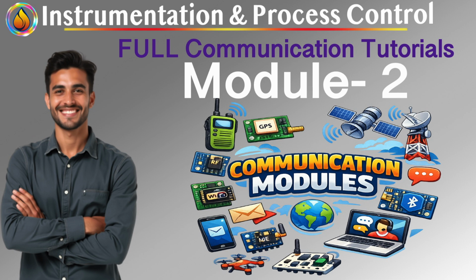RS232 didn't betray you. It simply did exactly what it was designed to do in an environment it was never designed for. That's the engineering takeaway you should internalize. RS232 is not bad. It is honest. It assumes one device, one cable, one ground, one quiet environment. The moment any of those assumptions break, RS232 stops being engineering and starts being hope. This is precisely why industry moved toward balanced, differential multi-drop systems. And once you understand this, RS485 no longer feels like an upgrade. It feels like survival logic. That's exactly where we're headed next.